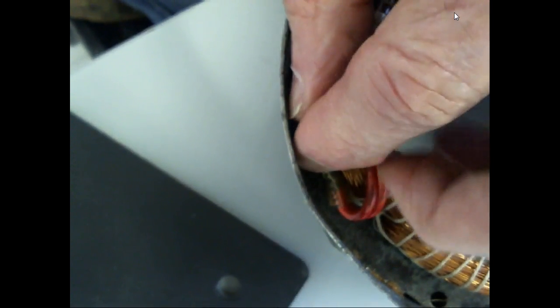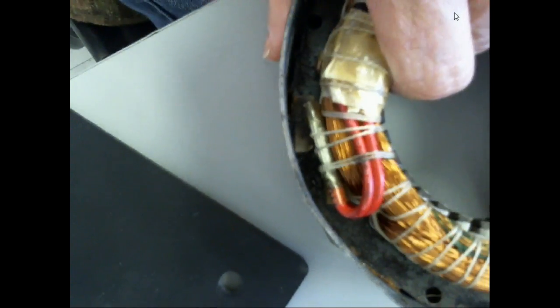And a lot of times when the motor goes bad, it's just that the little thermal overload's bad. You go in and you pay $200 or $300 for a new motor, you trade it in, and they take it and replace the overload on it. Starters is usually brushes. So that's all these wires. So this is for the capacitor, to create the phase shift. And then these wires over here, these are for your 3 speeds. So this is a 3-speed motor.